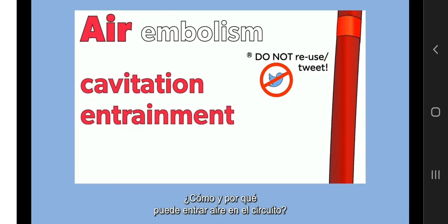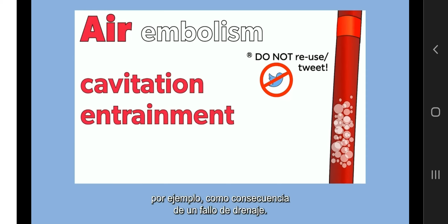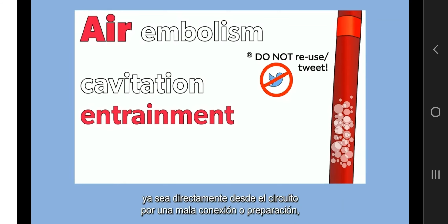How and why can air enter the circuit? Gaseous emboli may be produced by a phenomenon named cavitation, as blood is exposed to highly negative pressure, for example, as a consequence of drainage failure. When cavitation occurs, dissolved gases in the blood bubble out of solution. Cavitation rarely occurs with non-occlusive centrifugal pumps. Otherwise, air could enter the circuit from atmosphere, either directly from the circuit due to improper priming or connection, or due to a breach in the circuit, or from the patient, mostly from cannula and central venous line.